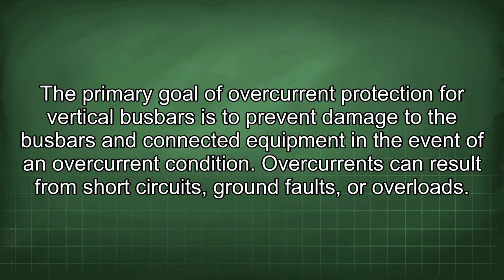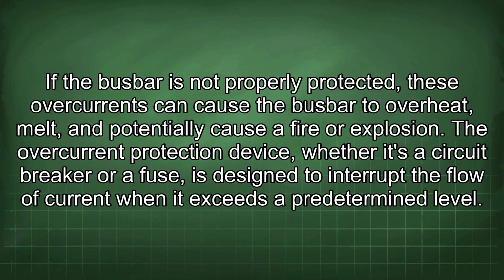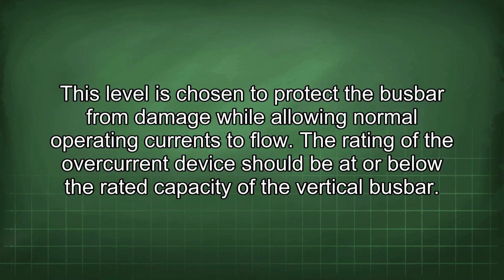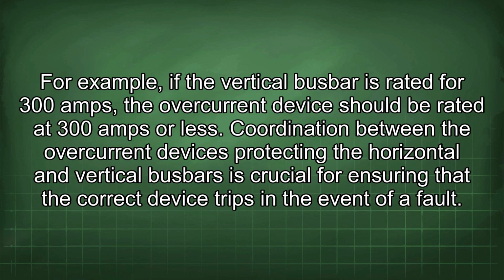Overcurrents can result from short circuits, ground faults, or overloads. If the busbar is not properly protected, these overcurrents can cause the busbar to overheat, melt, and potentially cause a fire or explosion. The overcurrent protection device, whether it's a circuit breaker or a fuse, is designed to interrupt the flow of current when it exceeds a predetermined level. This level is chosen to protect the busbar from damage while allowing normal operating currents to flow. The rating of the overcurrent device should be at or below the rated capacity of the vertical busbar. For example, if the vertical busbar is rated for 300 amps, the overcurrent device should be rated at 300 amps or less.